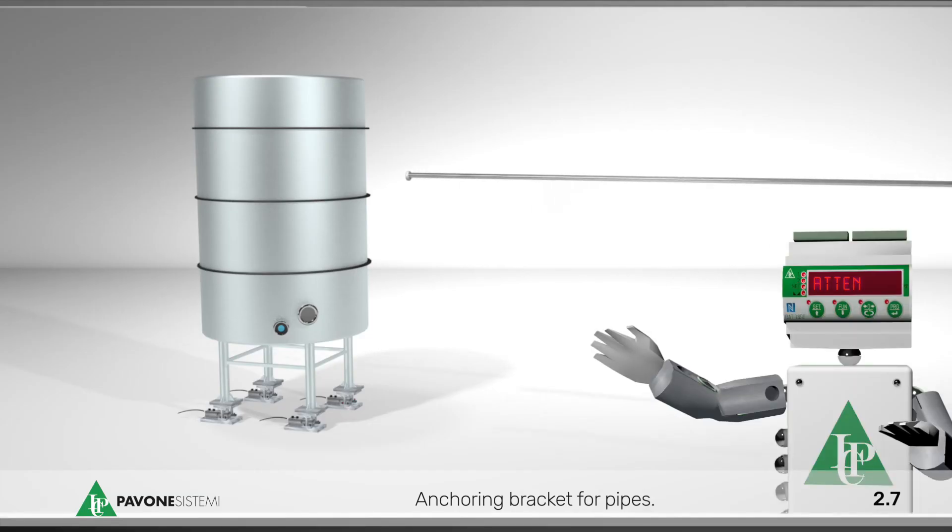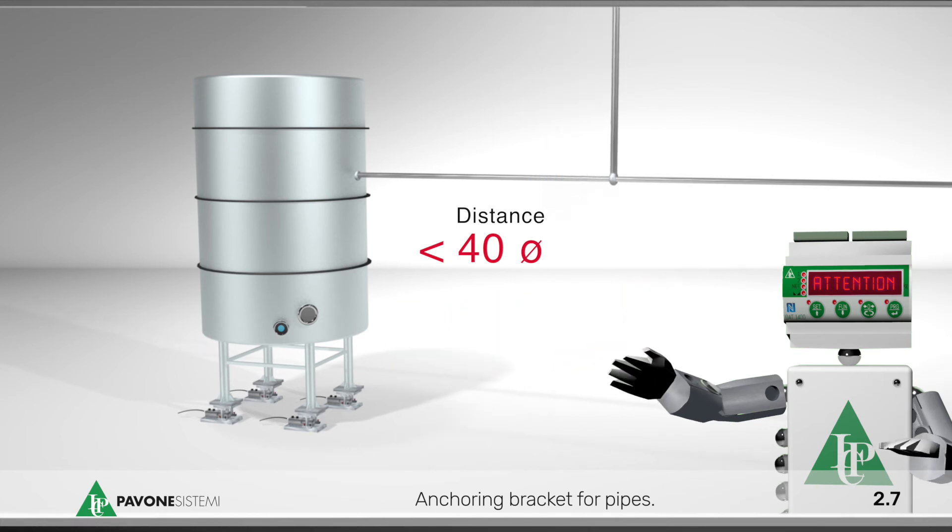Anchoring bracket for pipes. Alternatively, place the first anchored bracket in the horizontal section, as far as possible from the weighing structure at least 40 times the diameter of the pipe.